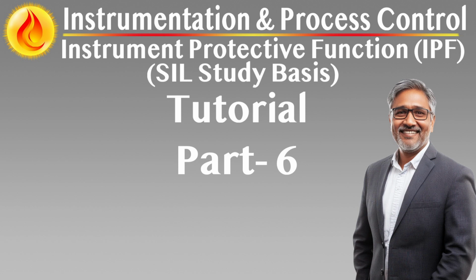Typical features of an automatic MOS. Predefined scope. Only specific designated IPFs or components, e.g., one transmitter in a 2oo3 sensor voting group, are eligible for automatic override. The MOS cannot be arbitrarily extended to other functions or hardware without revalidation.